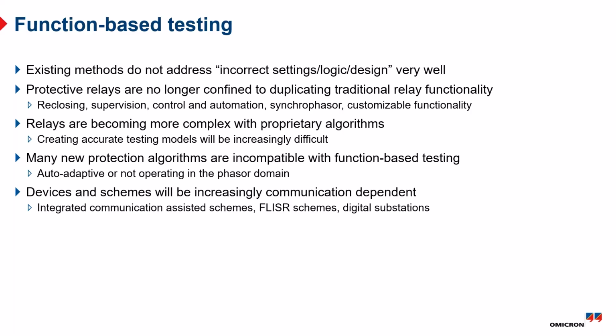Second thing is relays are becoming more complex. We're really venturing into some uncharted territory. Big one right now is time domain protection. Up until pretty recently, all protection is based on what we call phasors. So we basically have voltages and secondary currents. We calculate the RMS, the 60 hertz component of that waveform and the angle of that, and we compare that to the settings, and we make a trip decision.